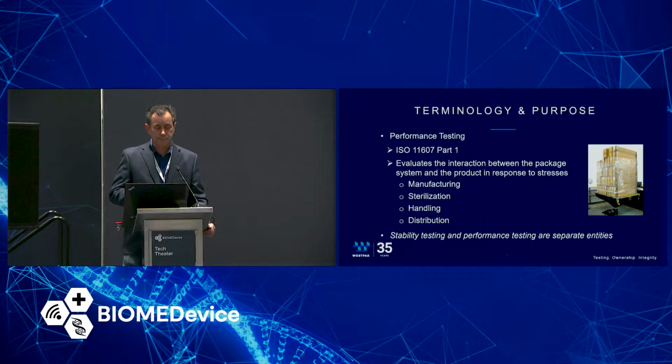So the key point from this is that stability testing and performance testing are separate entities. They should be conducted separately. One of the things that we have noticed is this separation over the years. The last couple of revisions have stated this. The buildup of stress in the package that occurs when both of these activities are conducted together could provide false positives. That means that you might have a defect when no defect would normally exist. So that's the purpose of separating these two activities.